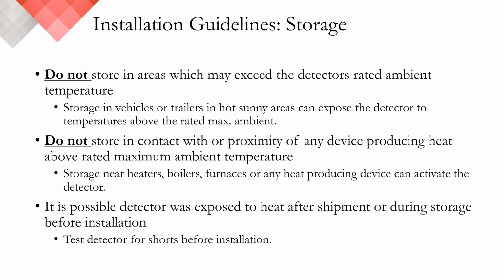Next, like the exposure in a hot vehicle, we want to avoid storing the detector near any heat sources, such as boilers or furnaces. Every lot of linear heat is tested before it leaves our facility. However, during the summer months, it's possible to expose the detector to heat while in transit. We provide instructions with every shipment on the proper techniques to test the detector upon arrival.